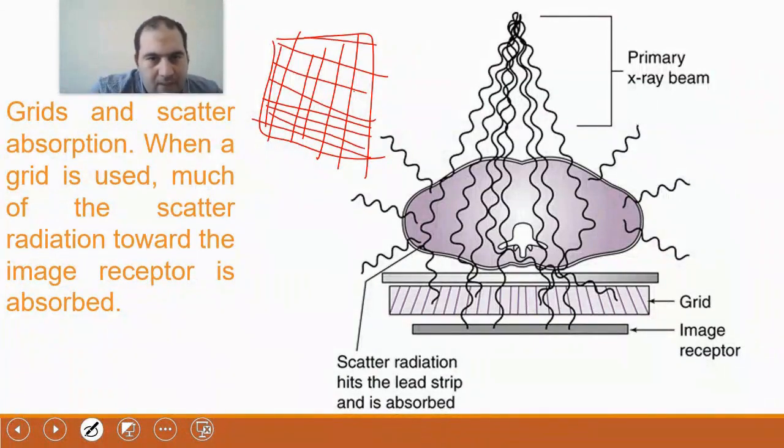The entire part that I have heavily shaded here, I call it like a grid. What does grid mean? It means that right now, for example, I will allow these holes to let through only the radiation that is incident and perpendicular to my film, while the radiation coming at an angle, like scattered photons, cannot pass through. I'm sorry. This is coming from a source. It can enter from here, but the radiation coming at a specific angle starts to hit the grid, which has a certain thickness between each hole that is enough to stop it.